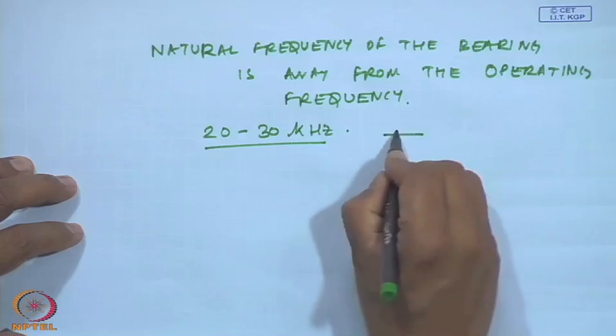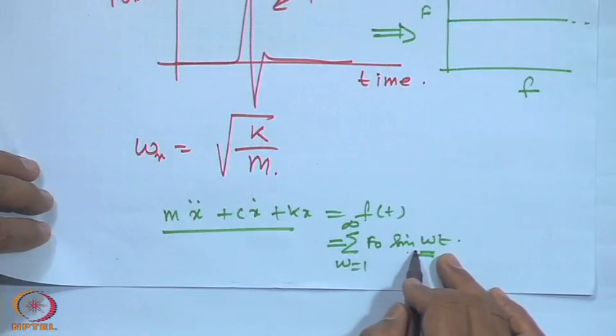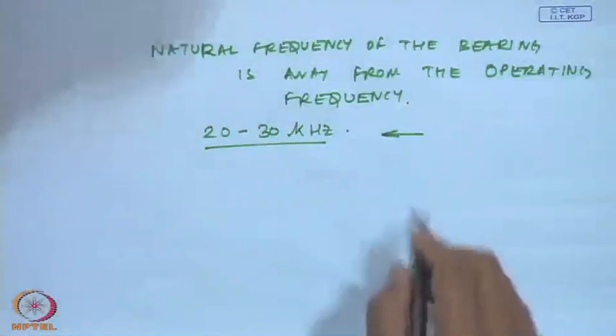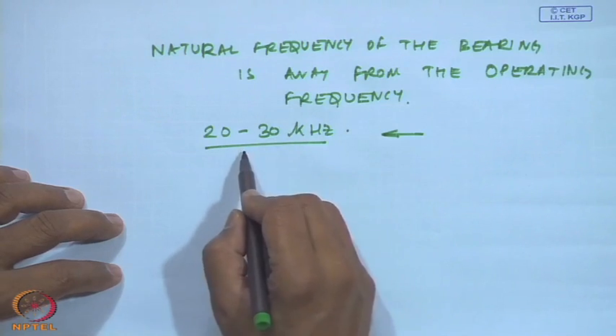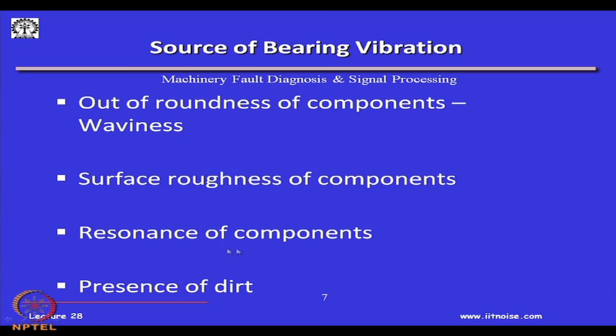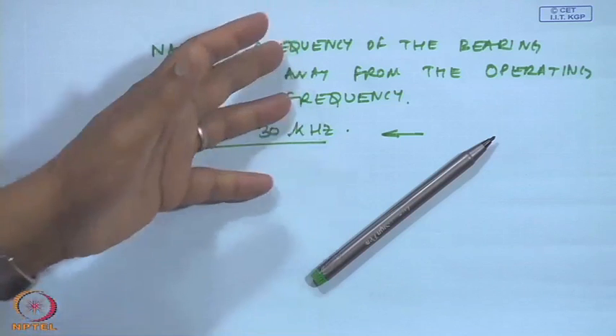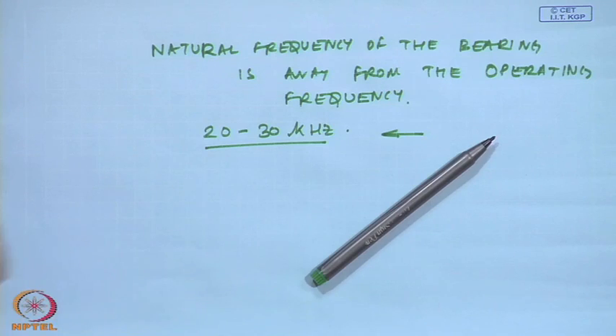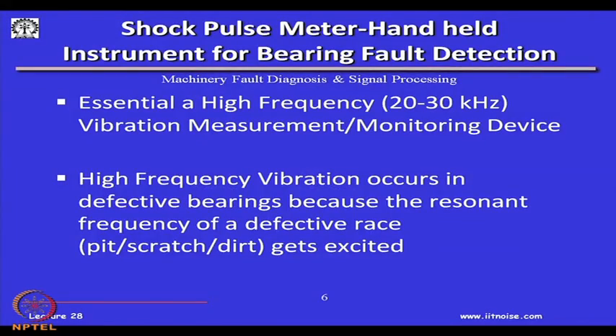But the problem is, because I have excited it here by an impulse force which has all the frequencies, the natural frequency gets excited. So, I will have a large response at its high frequency. Okay. So, resonance of components occurs. That means the bearings have got excited at their natural frequency. So, if I see a high frequency vibration in the order of 20 to 30 kilohertz in the ultrasonic range, if I see a high increase in the vibration level, I can say for sure a bearing has undergone a fault. Okay. And that is what people actually use in an instrument called a shock pulse meter. A shock pulse meter is actually nothing but a handheld instrument for bearing fault detection. It is nothing but a high frequency bearing vibration measurement, essentially a 20 to 30 kilohertz vibration measuring or monitoring device.